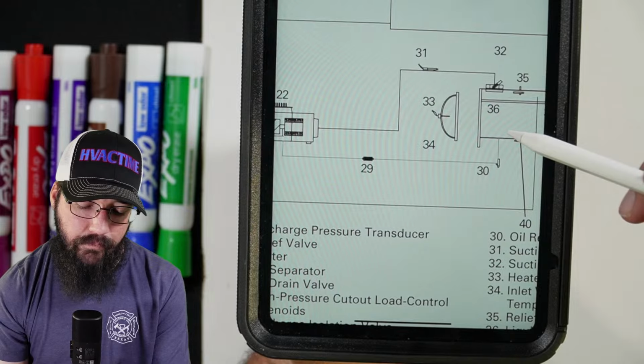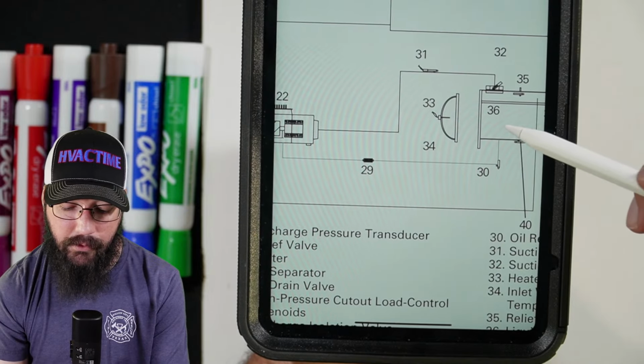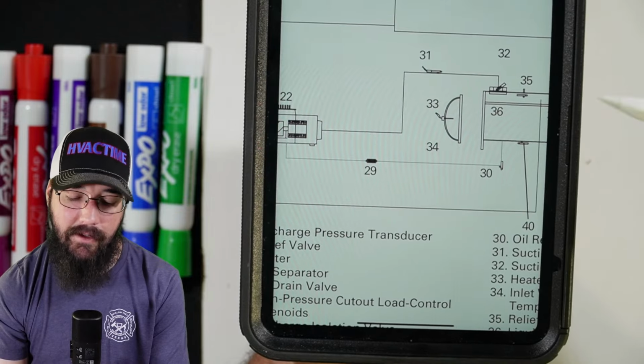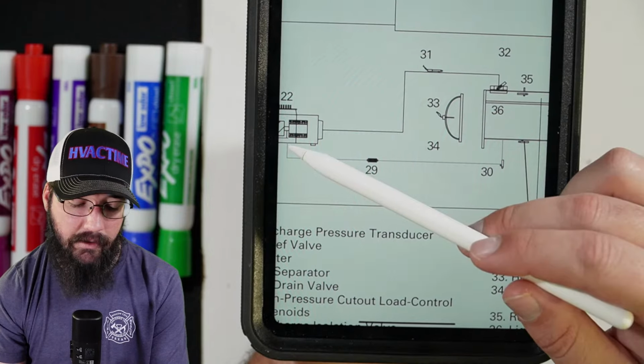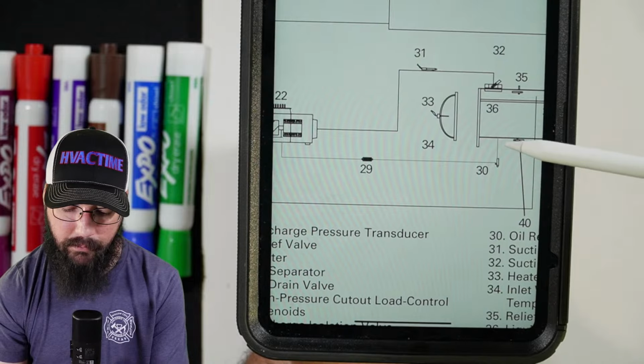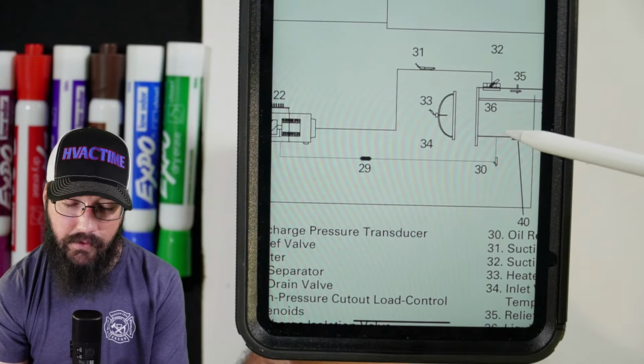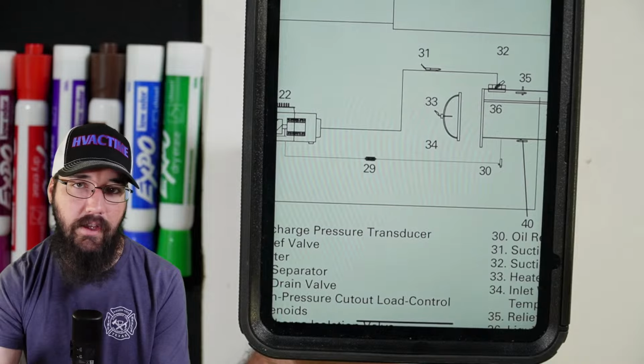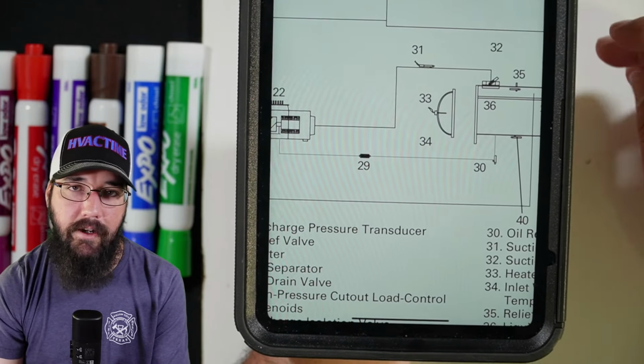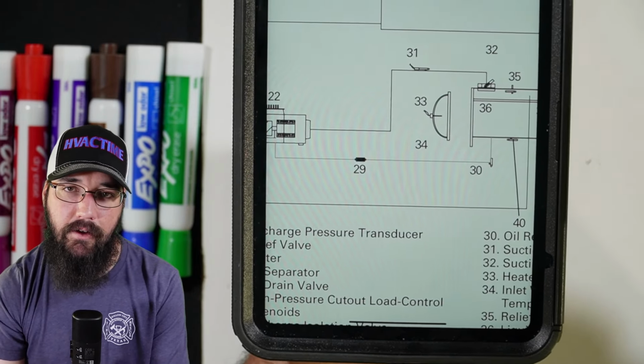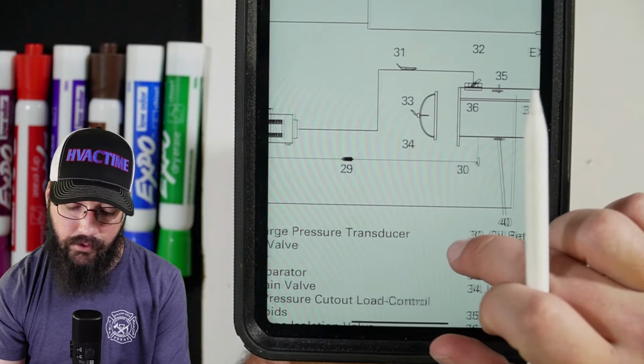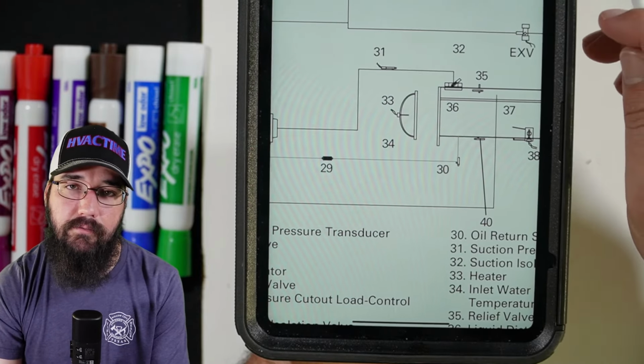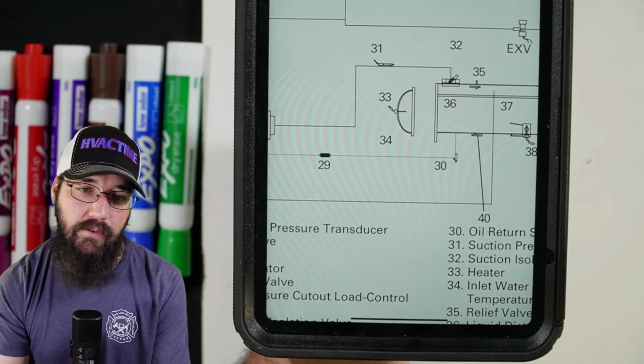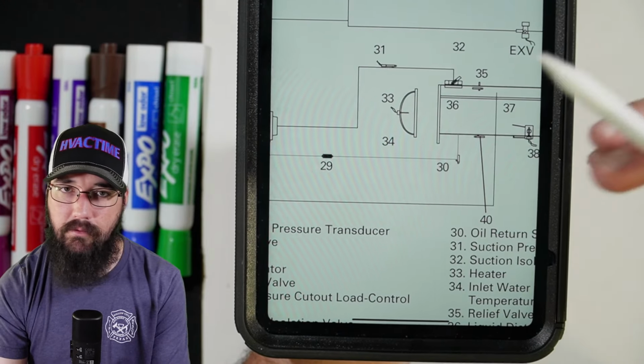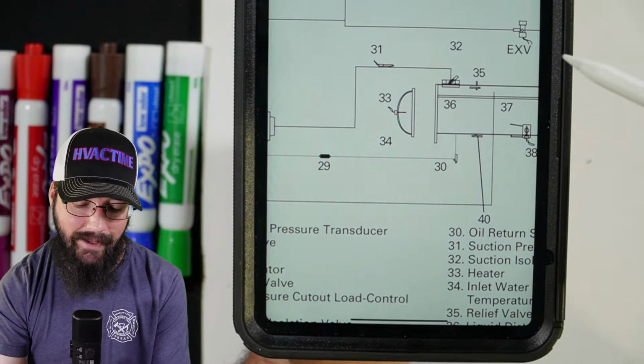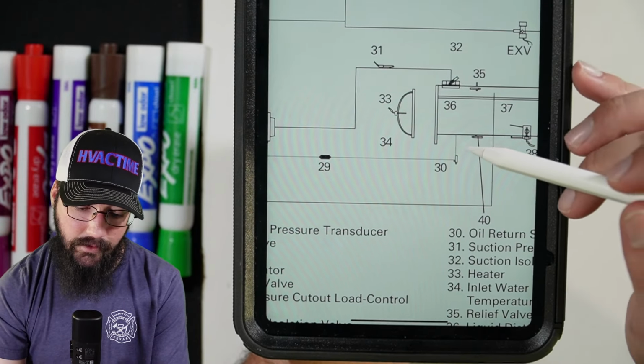Let's see. I mean, it's possible you could have debris. Like if you had some kind of debris get into the system to where it plugged up, it probably wouldn't make it to the compressor, but maybe over here in this area at the evaporator, where, I don't know, maybe somebody used some 515 or something on a sensor, and they've now got this big chunk of dried up 515 blocking the port. Like crazy ridiculous stuff like that can happen. Does happen.